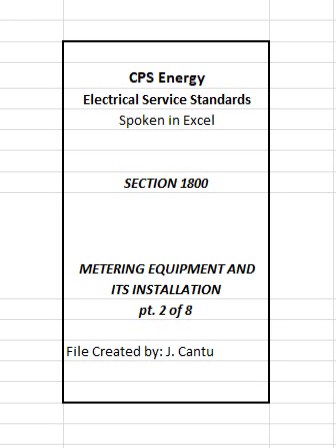There are various methods of installing instrument transformer rated metering equipment that depend on the service voltage, type of service, etc. This article covers typical applications of this type of metering equipment along with its general installation requirements. Instrument transformer rated metering and enclosures may be installed outdoors, in a standard weatherproof enclosure, in a switchboard or switchgear, or within the secondary compartment of CPS Energy's pad mount transformer. All jobs requiring instrument transformers must be closely coordinated with CPS Energy's customer service representative.